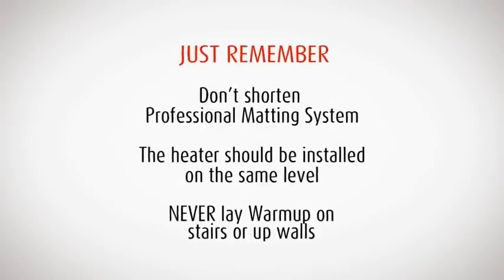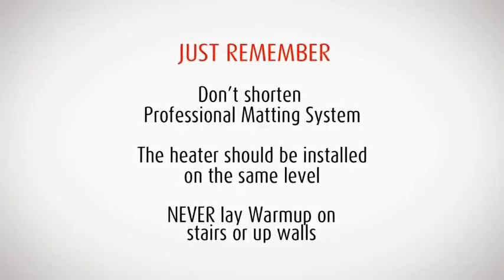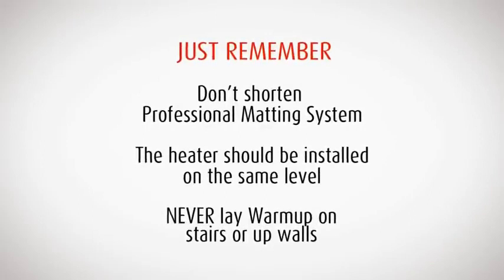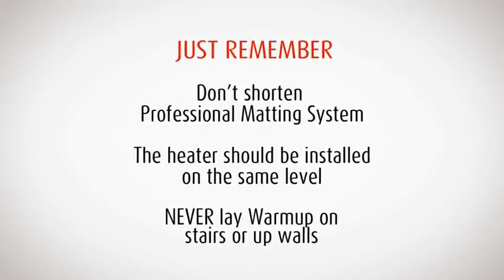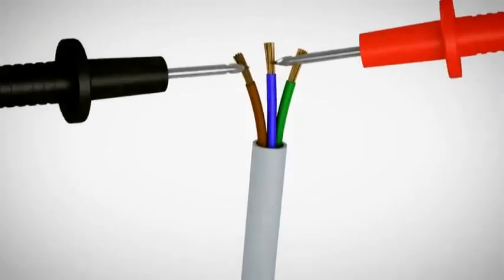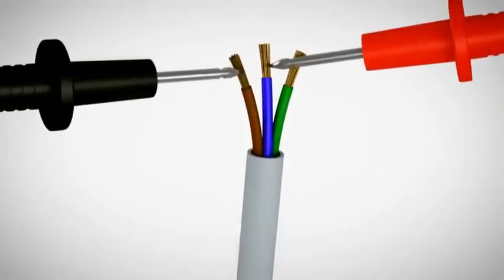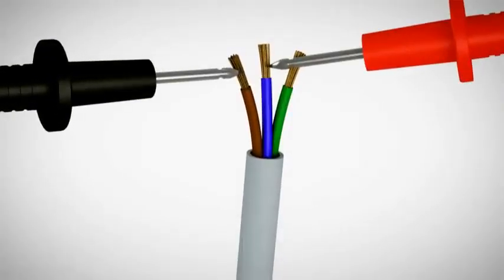Don't shorten the professional matting system. Each different mat is designed to produce a specific amount of heat. Perform another multimeter test to check that the heater has not been damaged and make a note of your reading in the Warmup installation manual. If your reading has changed, call Warmup immediately. Do not continue working.